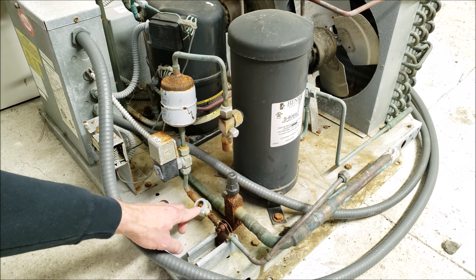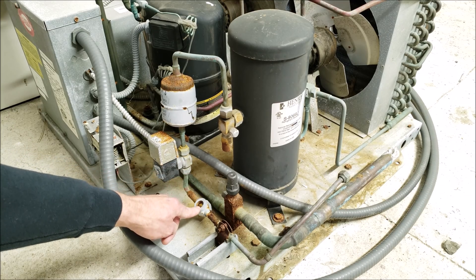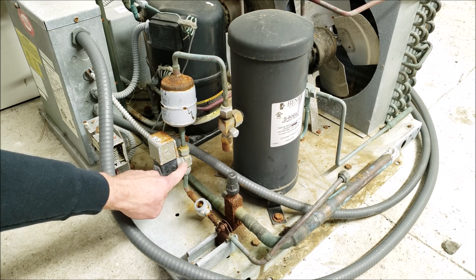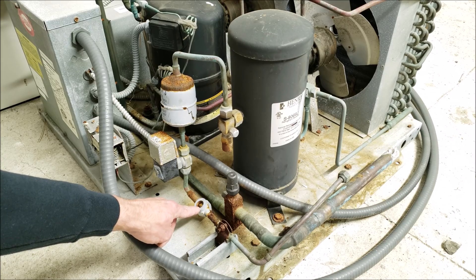The second reason you want the sight glass after the solenoid is: when the solenoid shuts off the liquid flow, you can watch the sight glass and make sure you don't actually have a little bit of liquid getting through. So if the solenoid gets hung up partially and isn't completing its full pump-down procedure, you'd be able to tell by looking through the sight glass.